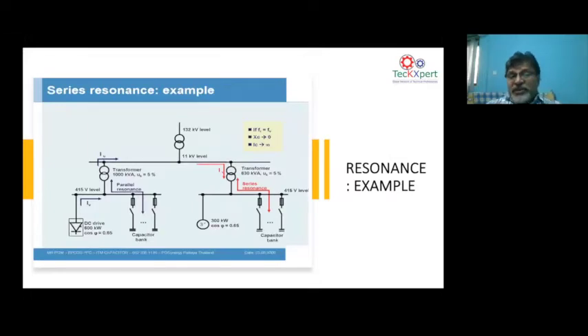There is also one more type of resonance called series resonance. I don't want to go into the details of this. If you simply look into it, you can see that the capacitor sitting in your plant is in series with the transformer, and then the rest of the impedance can create a resonance phenomenon in series. When you say series, the entire network impedance and the capacitive impedance can become equal and opposite, and it can also create a very high inrush of current.